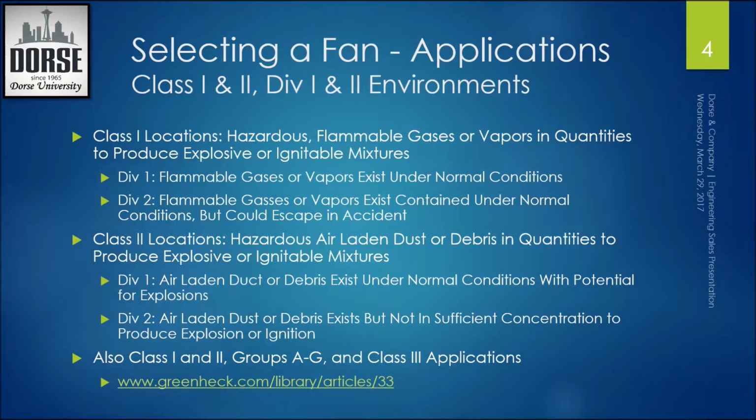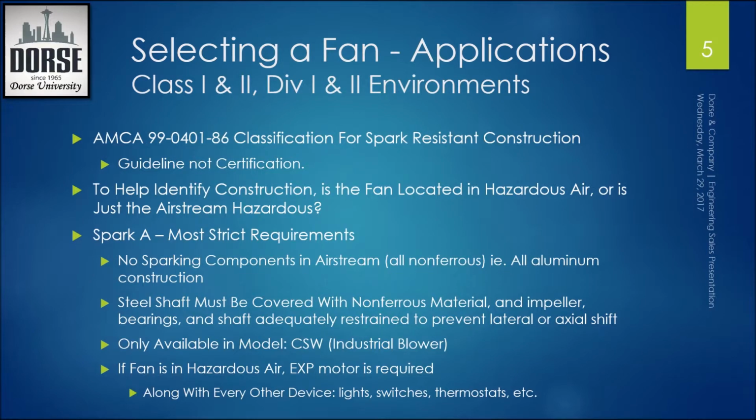And then there's also groups A through G and class 3, and there's a lot more detail to it. Those are just the class 1 and 2 and div 1 and 2 that we see a lot for explosive type environments. So I encourage you to go to that link there at the bottom of the page. Greenheck's done a great article and a great write-up that goes into so much more detail on all of these classes, divisions, and groups. So like I said, AMCA has classified what spark-resistant construction is, but it's not a certification, it's only a guideline.